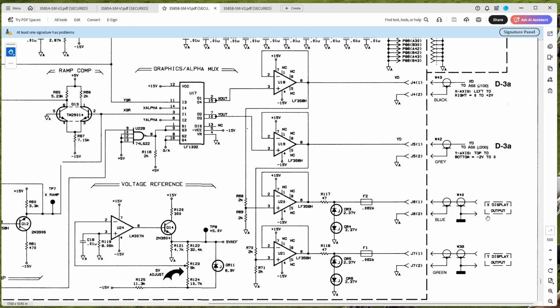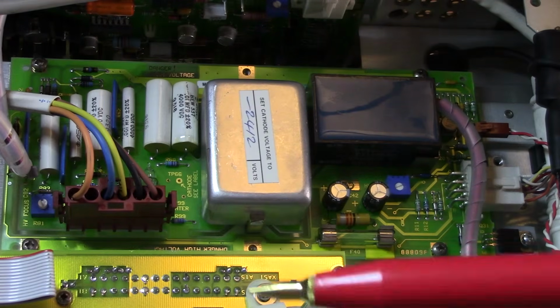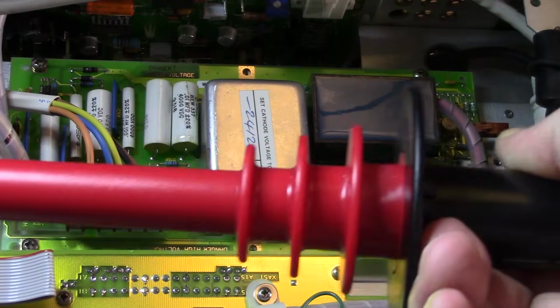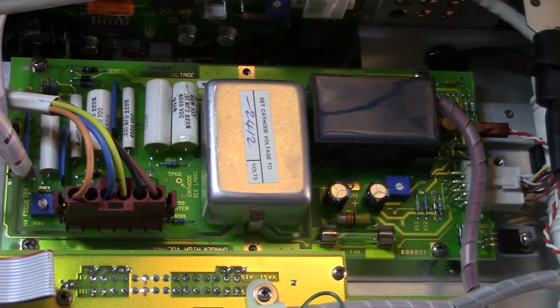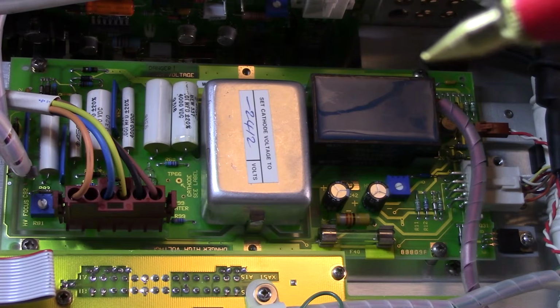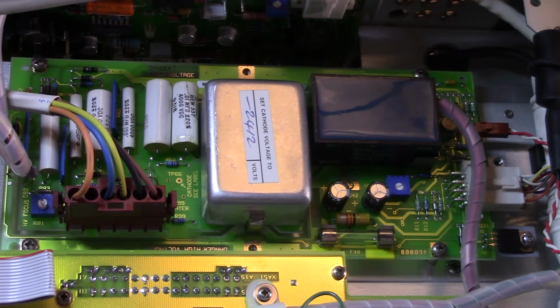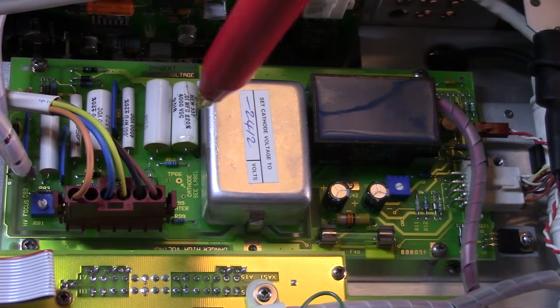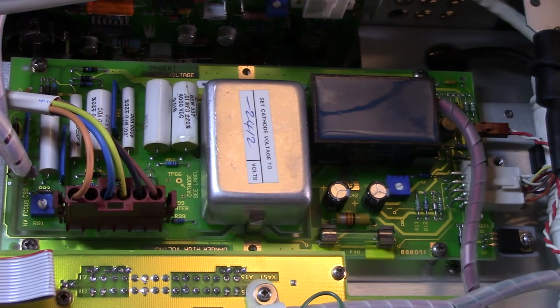So what I want to do now is check to see if we're actually getting high voltage stuff. So let's turn this off and let me swap the probe over. For the digital engineer, this is the somewhat concerning part, the mildly disconcerting part of the whole process. This probe is a 1,000-to-1 probe, and it should allow me to probe the heater and the cathode voltage off this board. Now, there are actually 2 test points just in here for those 2 items.